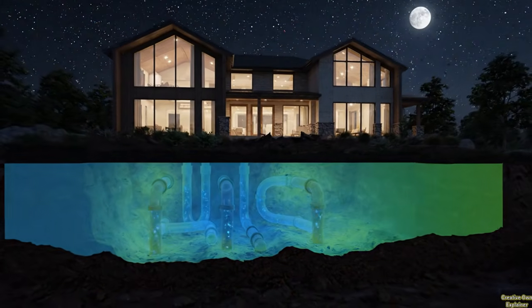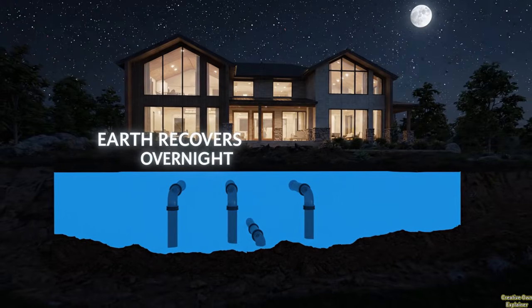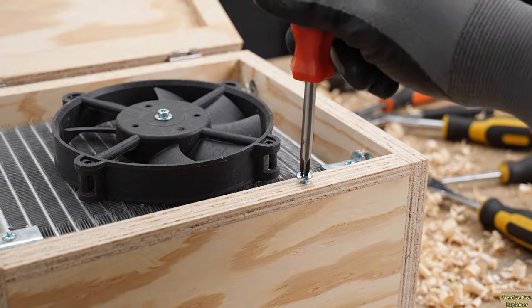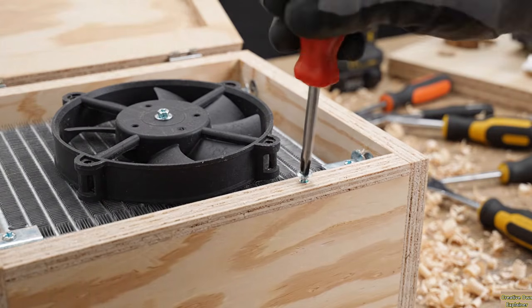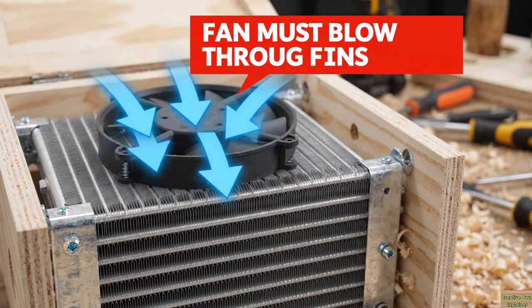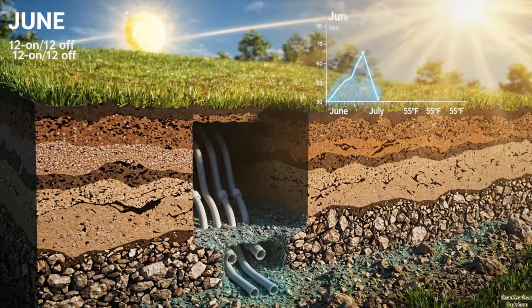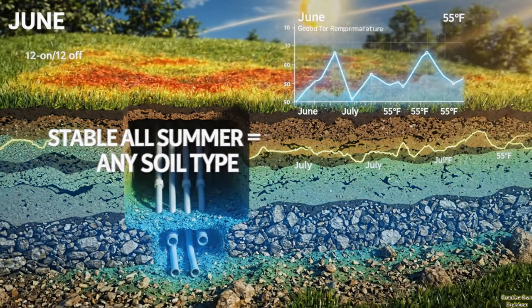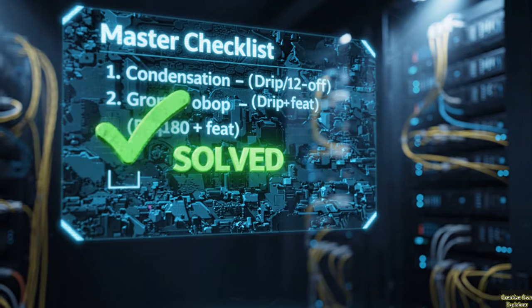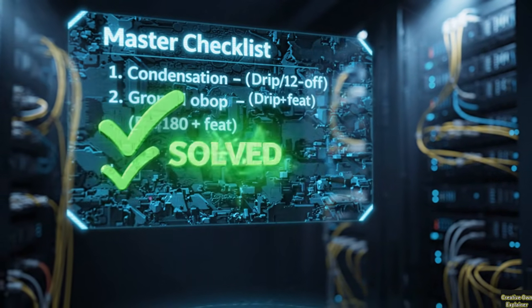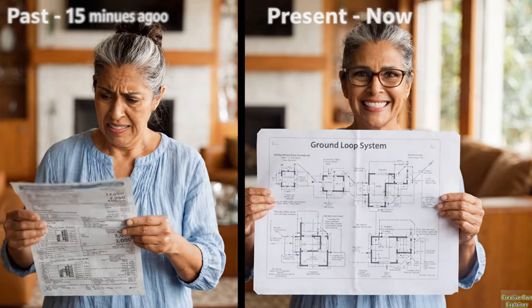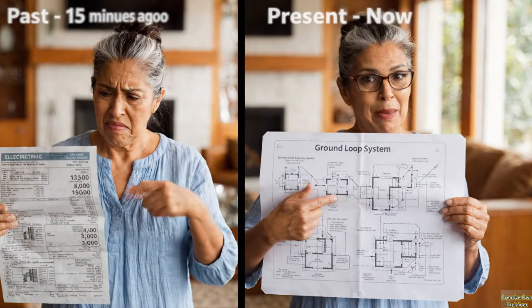The third problem is overloading the ground. If you run the loop continuously for the entire summer without any break, the soil surrounding the pipe gradually warms and your efficiency drops. The solution is simple. Run the loop during the day when you need cooling and let the earth recover its baseline temperature overnight. A 12 hours on, 12 hours off cycle is enough to maintain stable ground temperatures all summer in any soil type. Every failed DIY ground loop comes down to one of these 3 issues. None of them are physics failures. They are installation failures. And now you know how to avoid all 3.